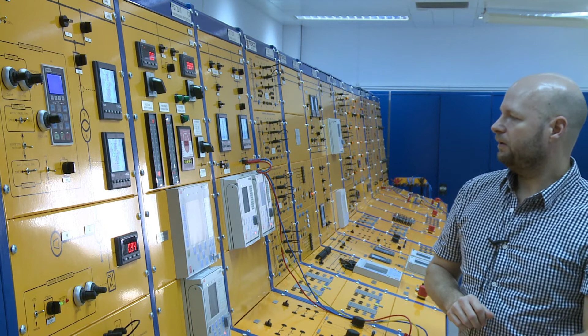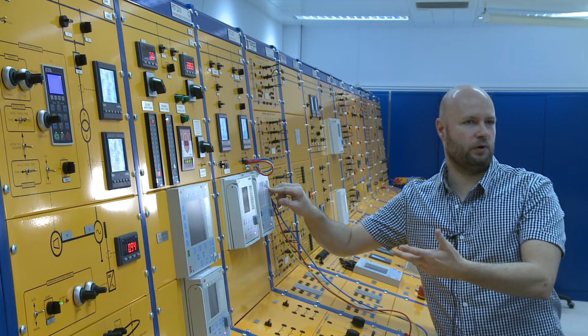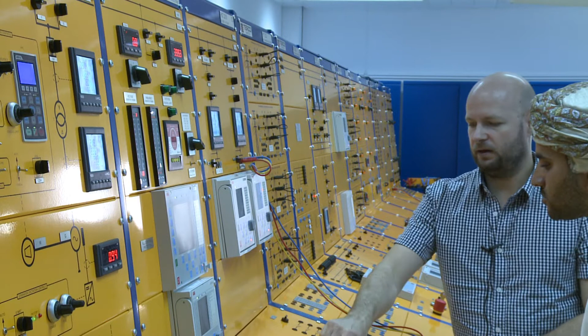Here we see we have a flashing red light on start earth fault. Once again, we've just had a start, so it's seen a problem, but the problem has disappeared before it has reacted and taken any trip. That's probably from when I connected or disconnected something, a balance maybe, so we can take this away just with trip reset.